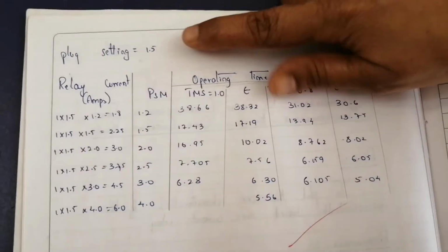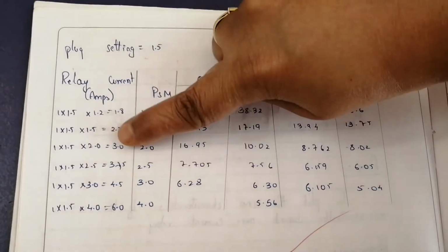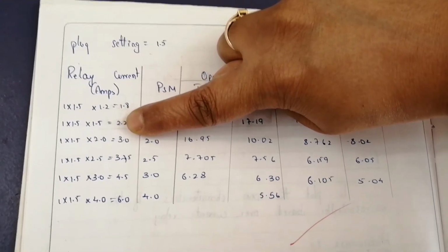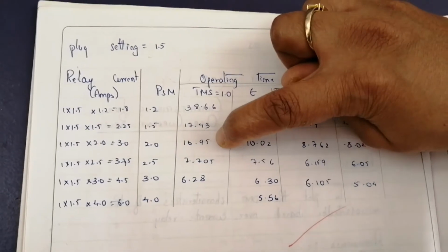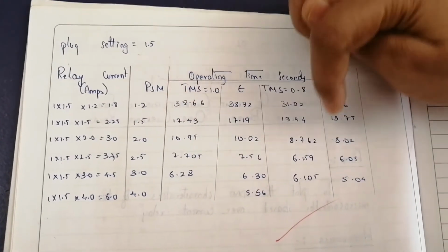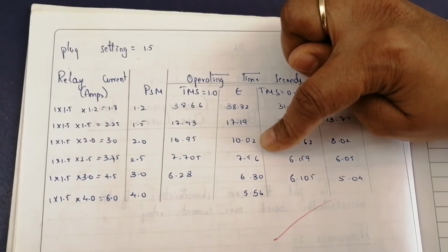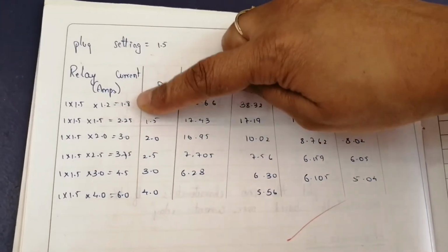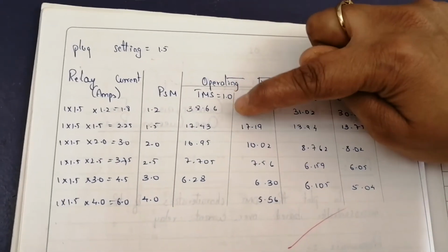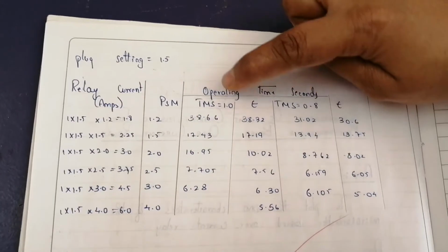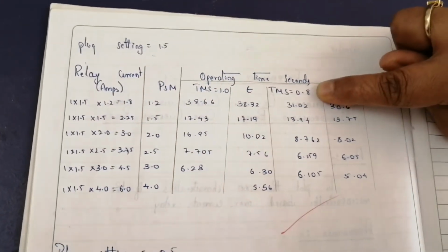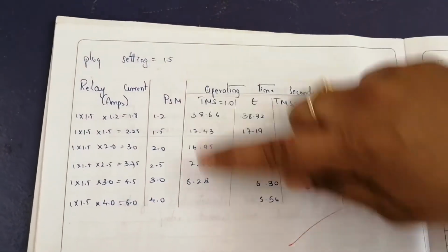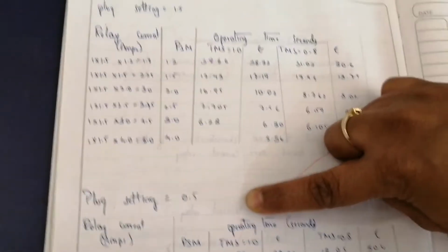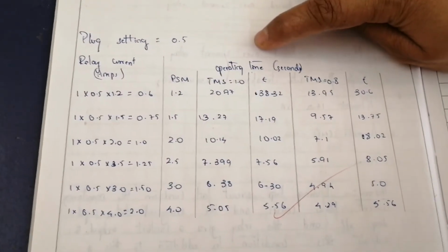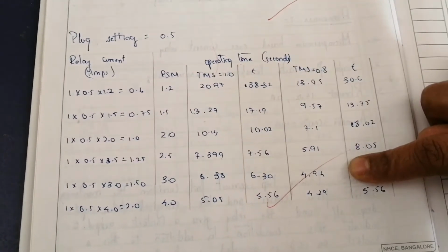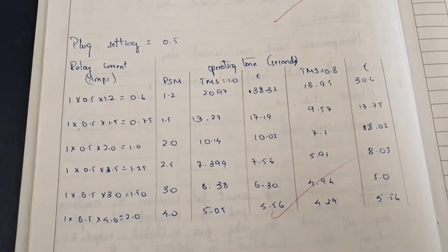You can see the plug setting 1.5, that is your phase current, and you can observe your relay current 3 amps is the relay current, and your operating time is 16.95 shown here, but there you have got 10.02. So at different values of your relay current, you have to perform the same experiment and note down the time. I have done the TMS at 1. I have to do the same way at TMS 0.8, and similarly at 0.5, plug setting 0.5, I have to repeat the experiment with all the steps, and finally I have to plot the model graph.